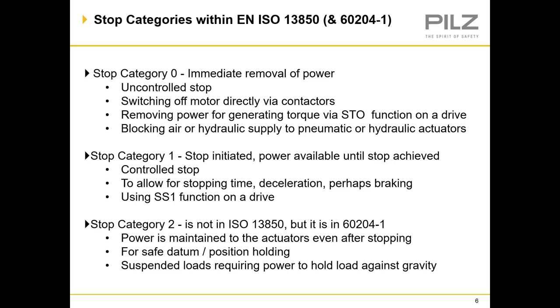Stop category 2 is not in standard 13850 but it is included in IEC 60204 part 1. Power is maintained to the actuators even after machine axes have come to a standstill. This is to be used if a safe position or datum position is required for position holding — it could also be used to hold against other forces such as gravity. Some variable speed drives are equipped with a specific SS2 function.